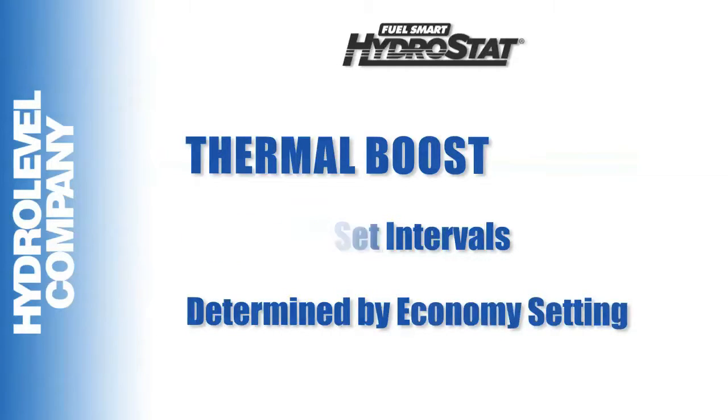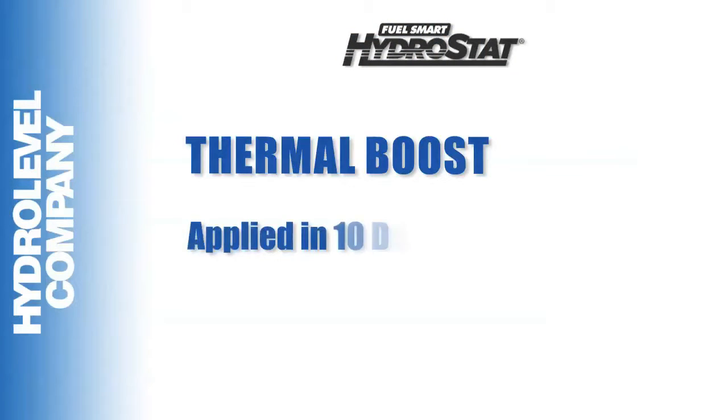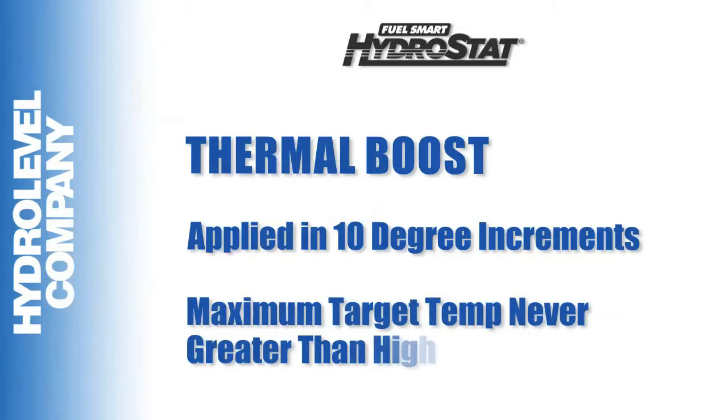A low setting will apply thermal boost at quick intervals, while a high setting will delay the boost interval, thus providing greater fuel savings. As an example, if the economy setting was at 1, the heating system may delay increase in the temperature by 15 minutes. If the economy setting were more aggressive, such as the number 3, the thermal boost delay would then be 25 minutes.